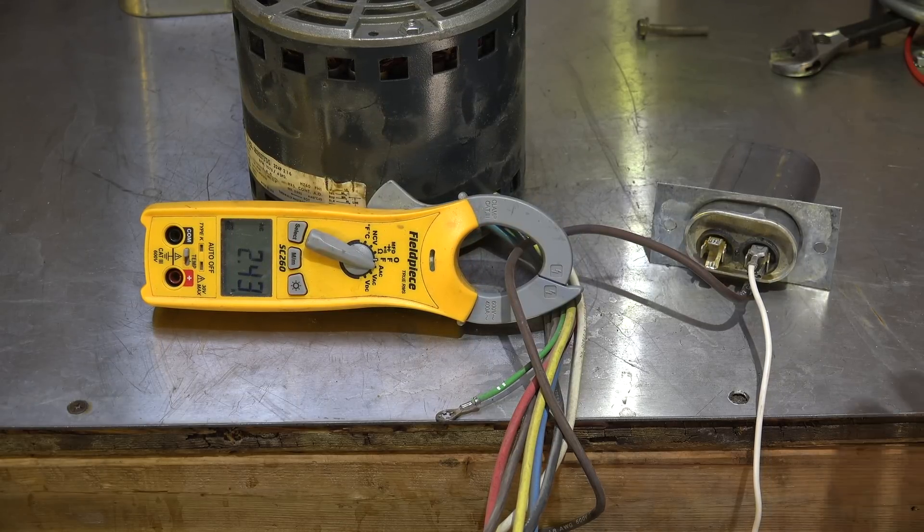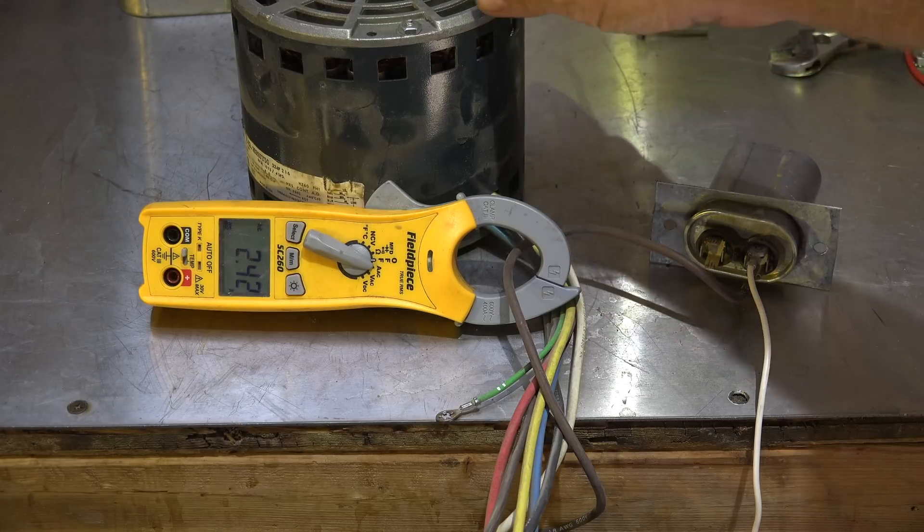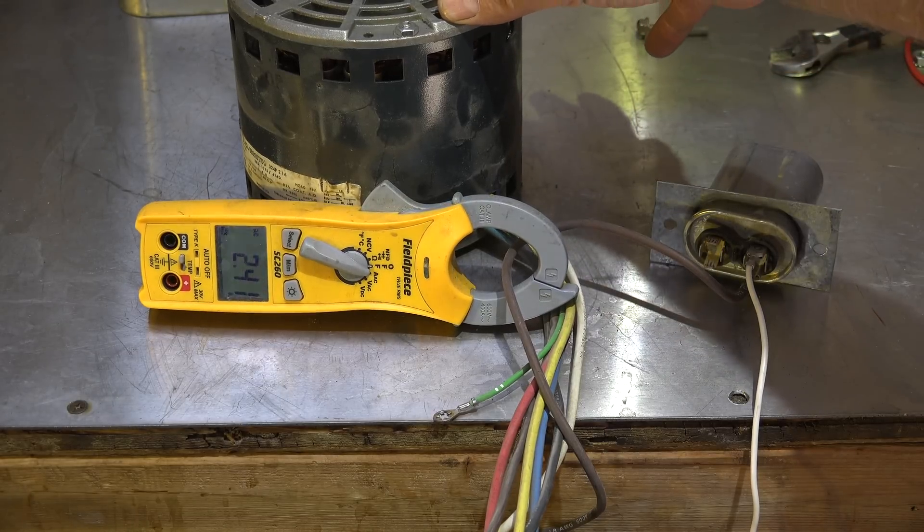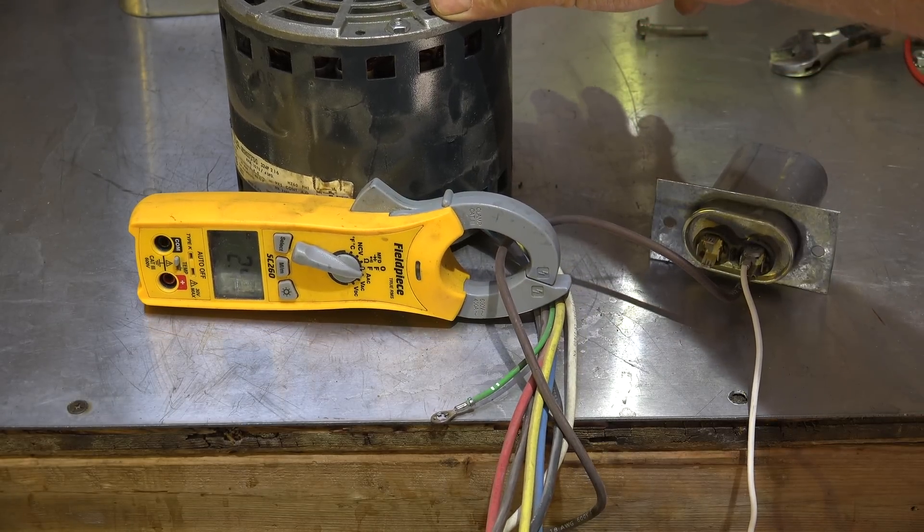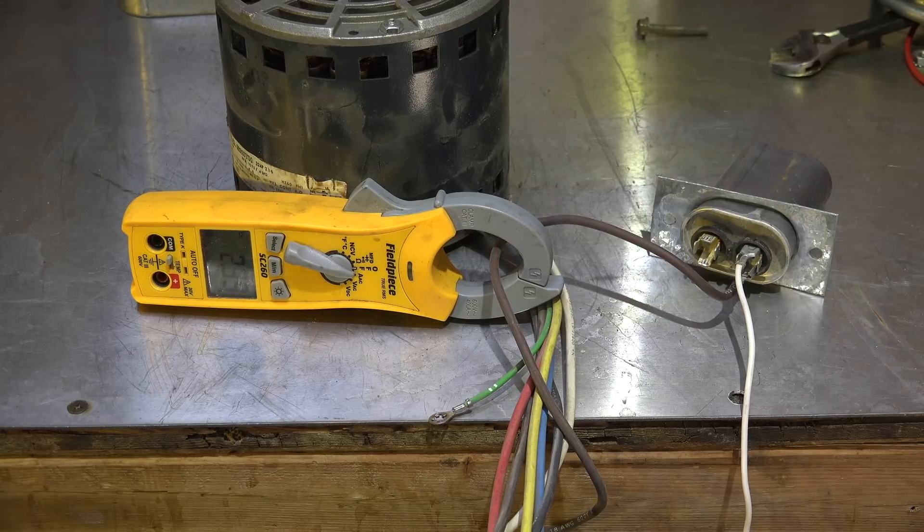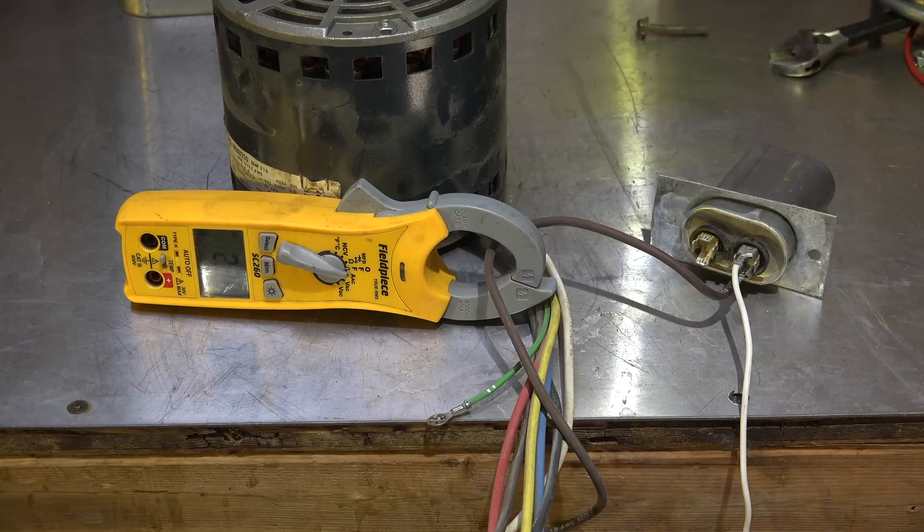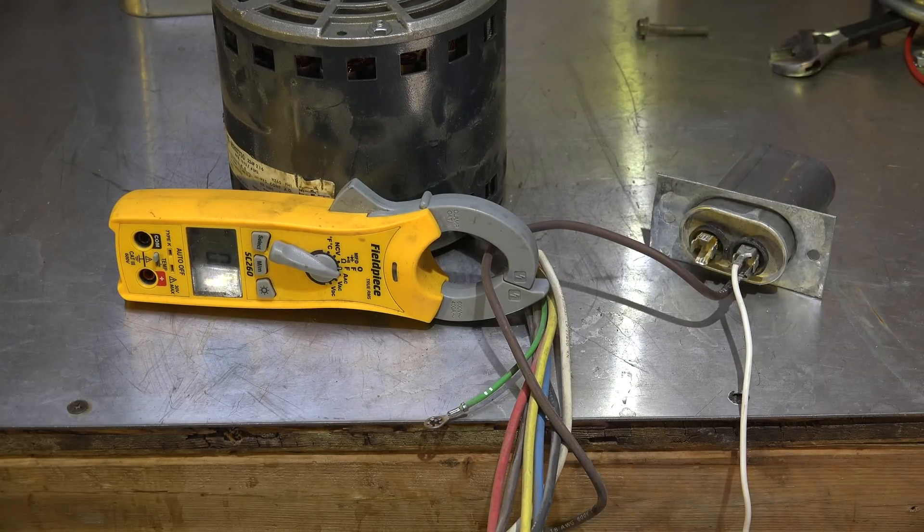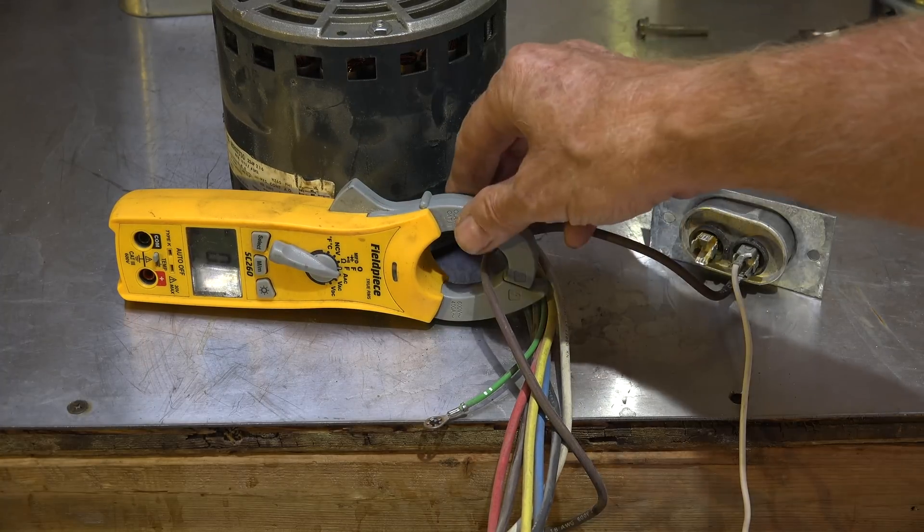And notice the noise the motor's making - a real humming sound. And it's making noise, it's not running efficiently. So when we put the run cap in the circuit...